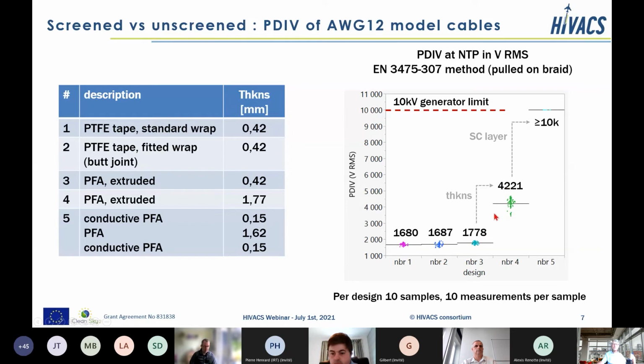But the voltage is only increased roughly by a factor of 2. And then we have the 5th cable where we have added the semiconductive layers. And here the partial discharge inception voltage is above the limit of our generator. So it's above 10 kV. So we don't know what the actual value is.